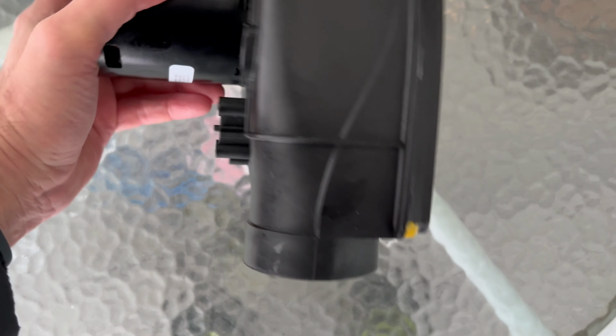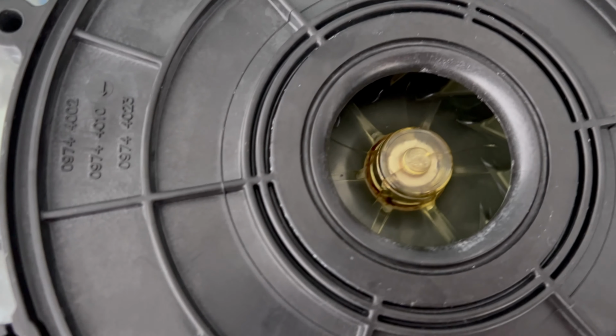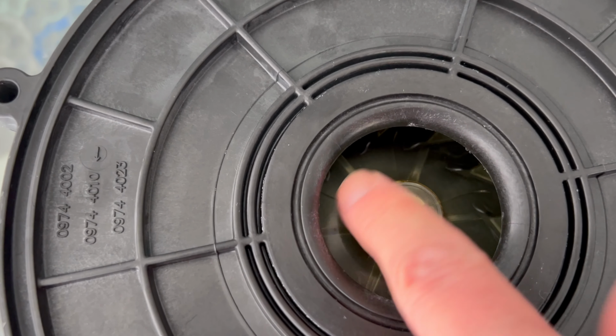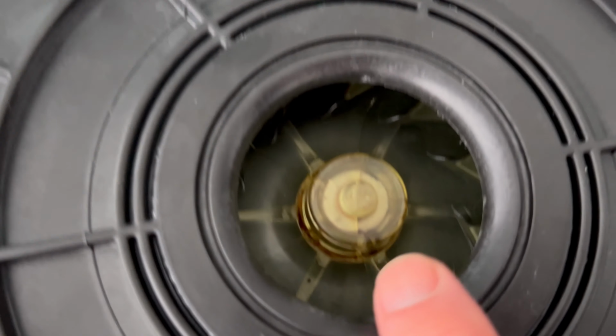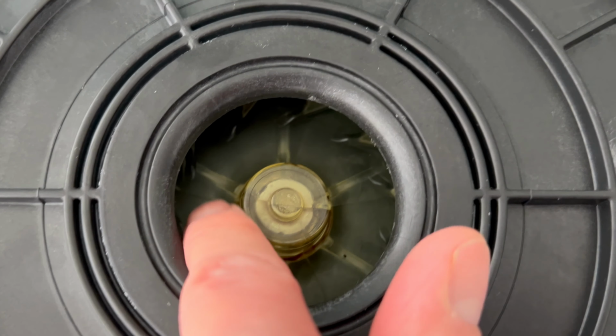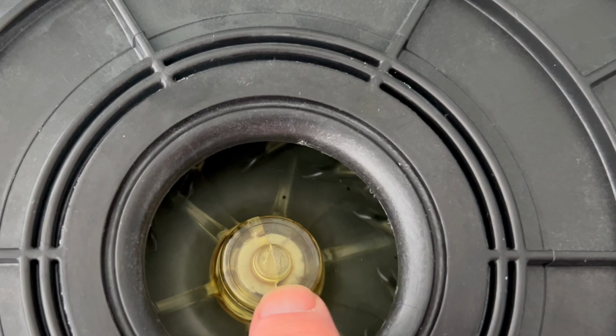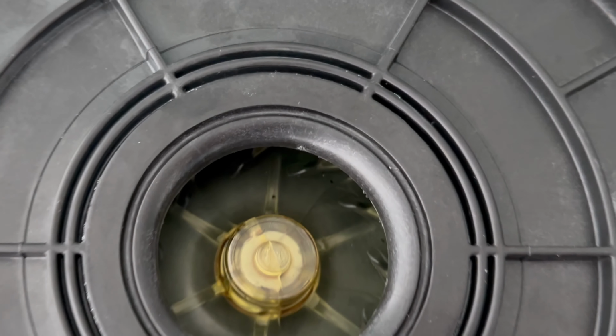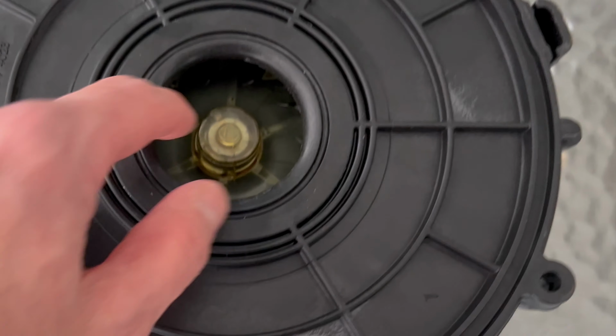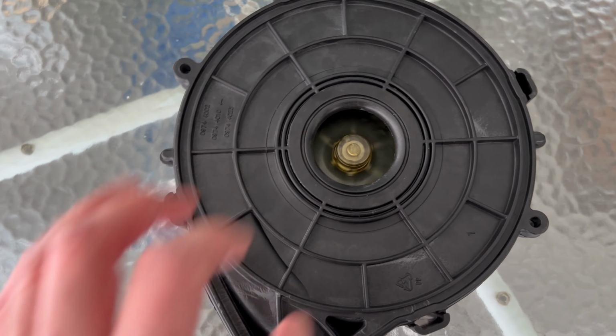Okay, and here we have the broken so-called inducer fan. Well, I should not say broken, but what you see here, the impeller wheel has little cracks. See that? Just tiny cracks, but the problem is that thing spins. You see that crack here, for instance, and it has several of these cracks, like one here. So that wheel, that impeller, spins at 3000 RPM.